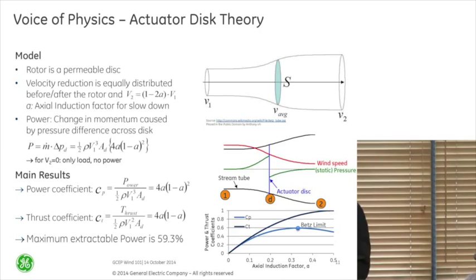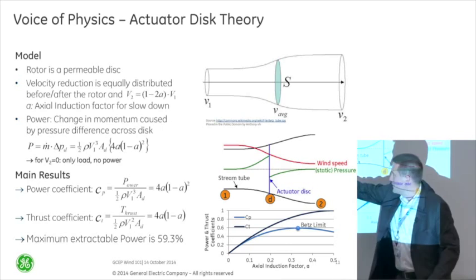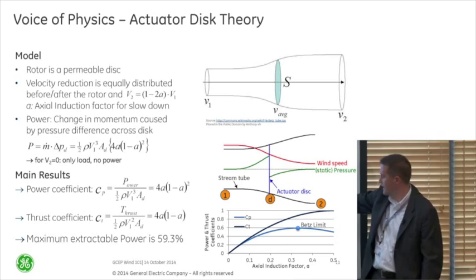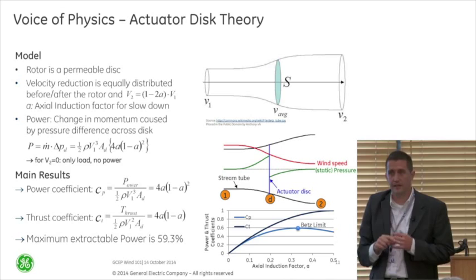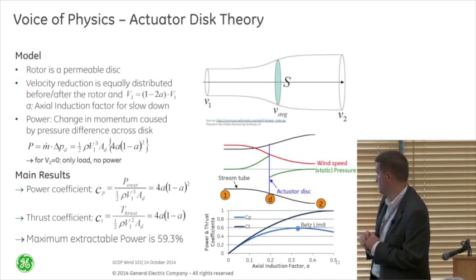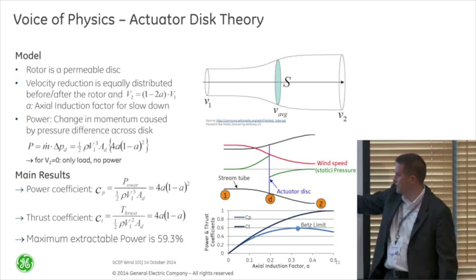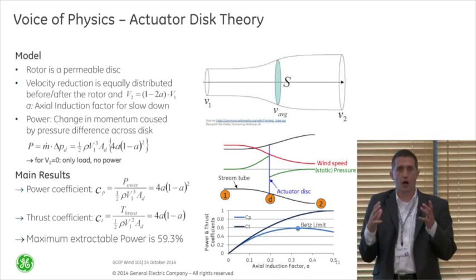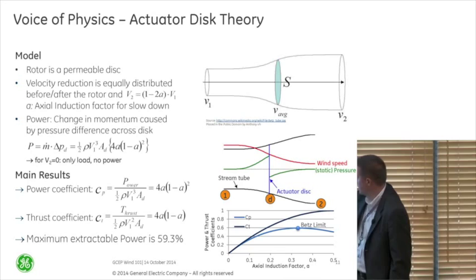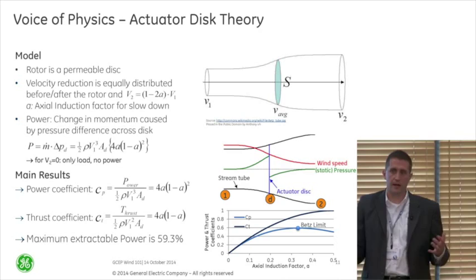Working through the derivation with the axial induction factor A — which is the ratio of speed reduction at the disc versus the upstream speed V1, with V2 being (1-2A) times V1 — you can substitute into the power equation and find what the power coefficient CP looks like as a function of A. The result is CP equals 4A times (1-A) squared. If you plot it across axial induction factors, it maximizes at around 59.3%, which is the Betz limit. No wind turbine has ever exceeded that. State of the art today is around 51 or 52%. Typically turbines run around an axial induction factor of 0.3, because continuing to higher A increases thrust and cost without much additional energy benefit.